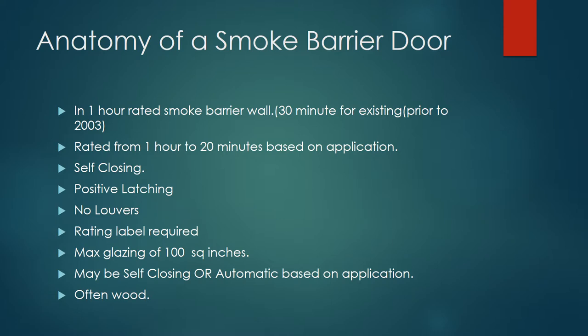With smoke, there's no heat to close a fusible-linked louver, so louvers are not permitted on smoke doors. This creates problems when spaces are converted — for example, when a server or electronic equipment with heat load is placed in a room never intended for it, and staff try to add louvers for ventilation. If it's a smoke door, you simply cannot do it. Rating labels are required for smoke barrier doors, and maximum glazing is typically 100 square inches.